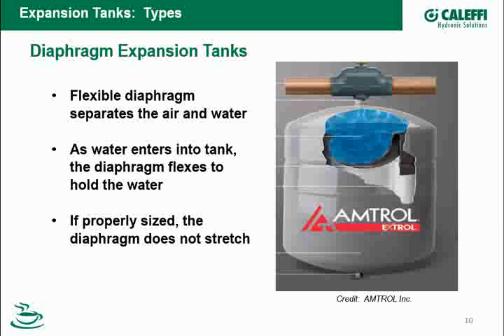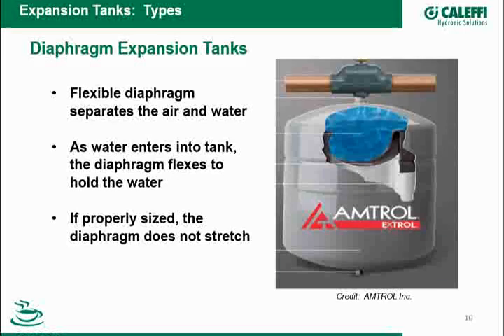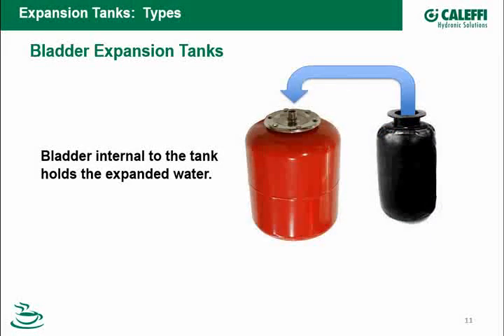Now, the other option is the bladder expansion tank. Instead of having a flexible diaphragm, it has a flexible bladder that sits down into the tank, water connection on the flangeway here, so the water's going down into the bladder, the air surrounds the bladder in the tank. So with this, it works very similar to the diaphragm tank. The water comes into the bladder, but now rather than flexing the diaphragm, it's either expanding the bladder out to its original shape or being pushed back in by the air charge in operation.